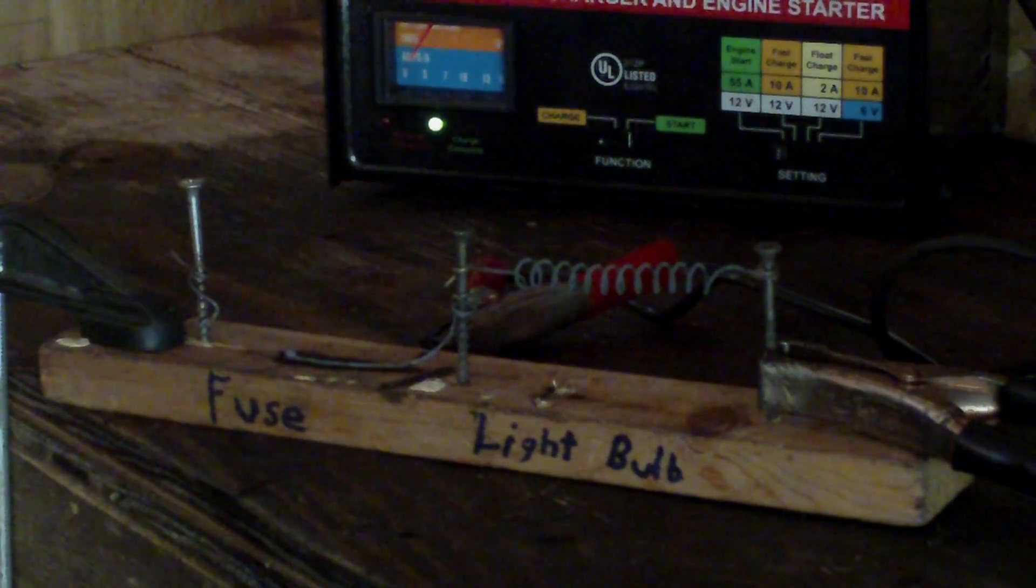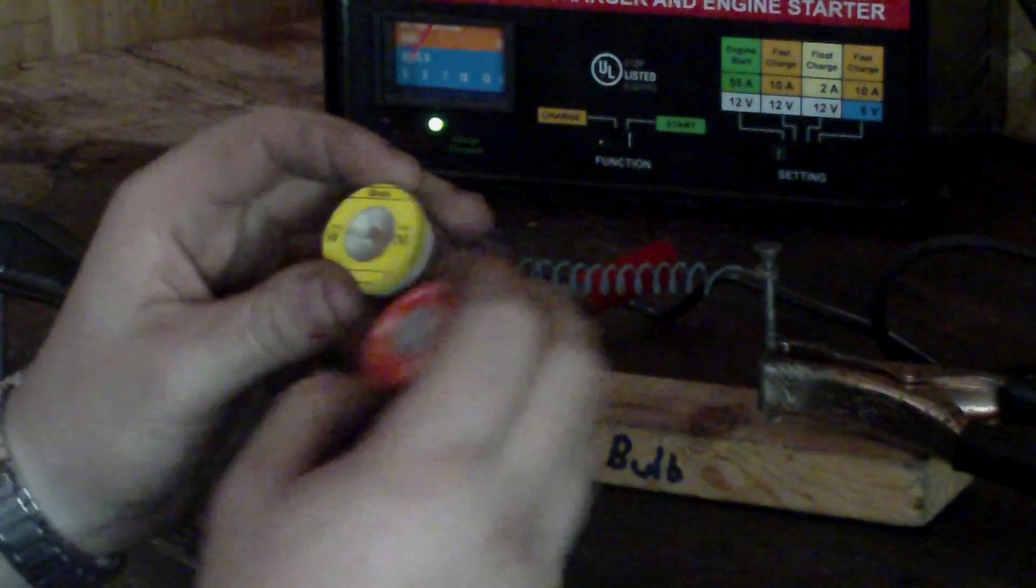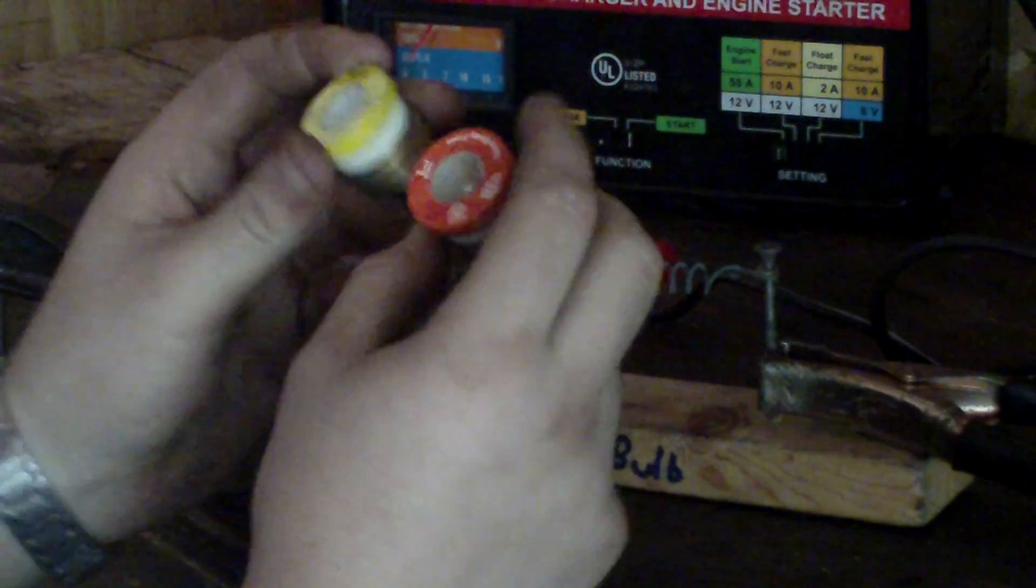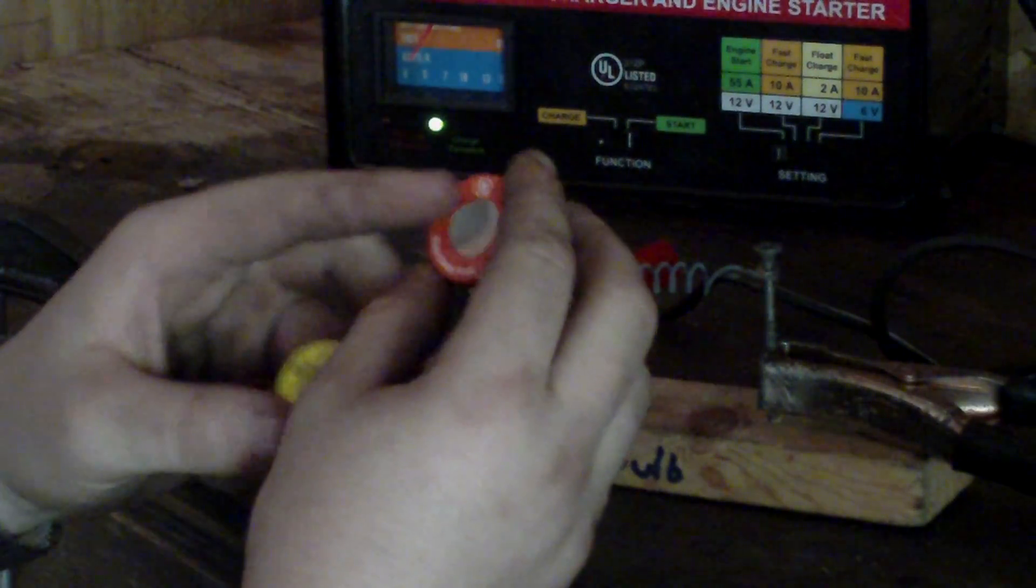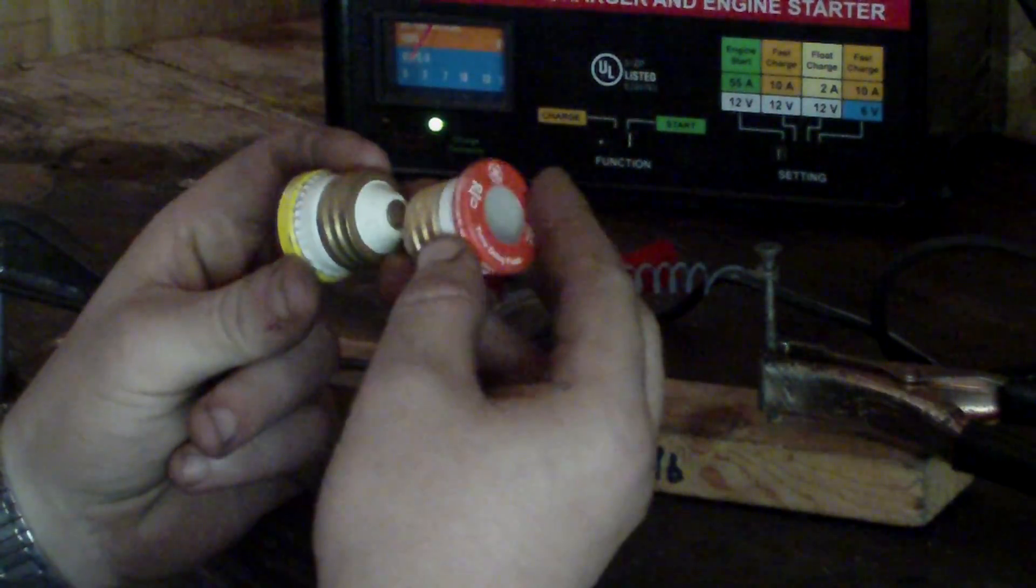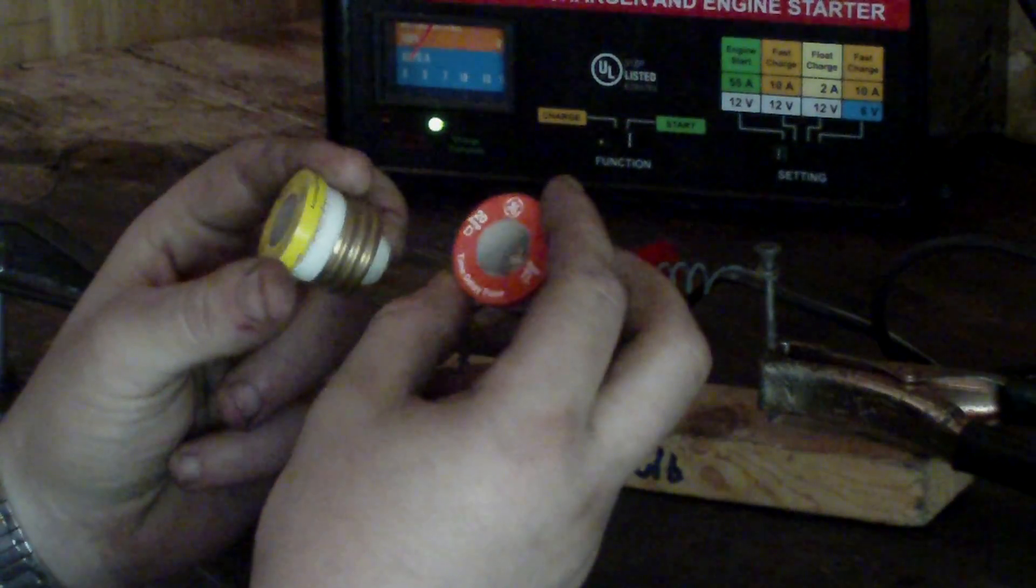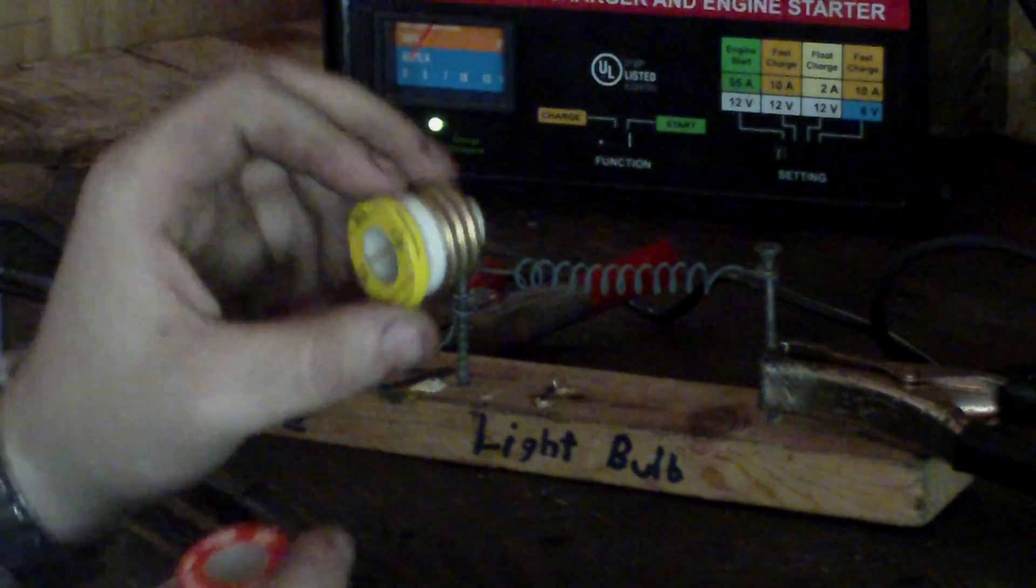And your fuses come in different sizes and shapes. Your smaller fuses that are in older homes were these Edison type fuses. This is a 30 amp. This one's a 20 amp. And that brings up another point. If your house has fuses and you blow a 20 amp fuse, a 30 amp fuse will screw into it.